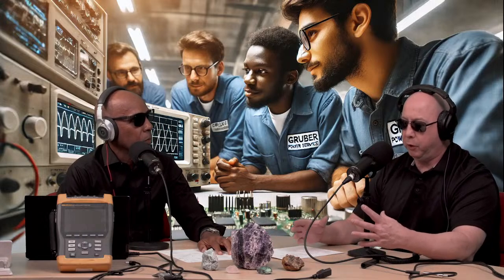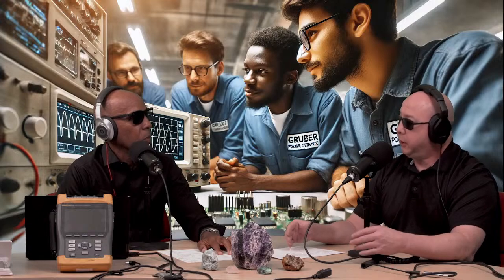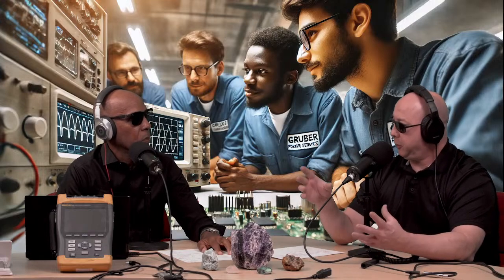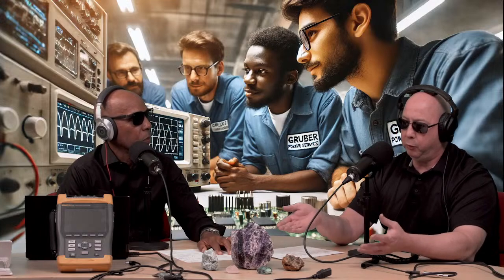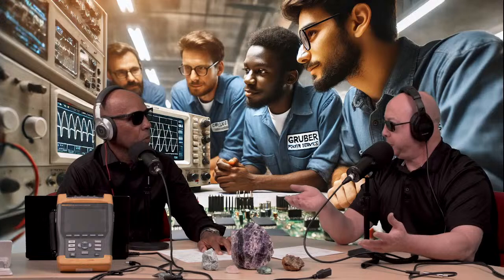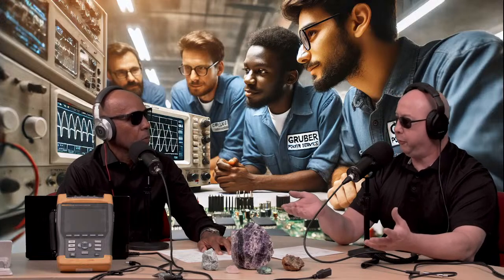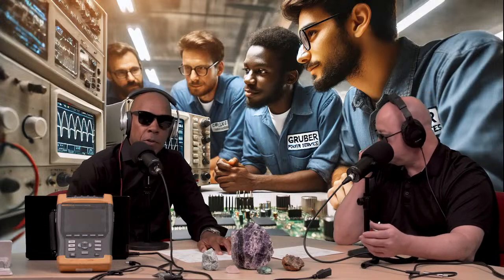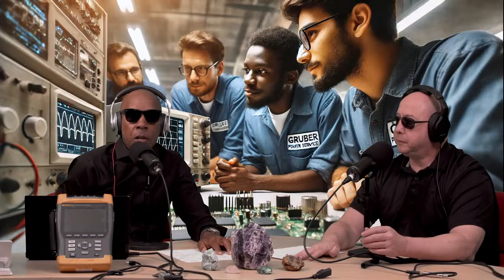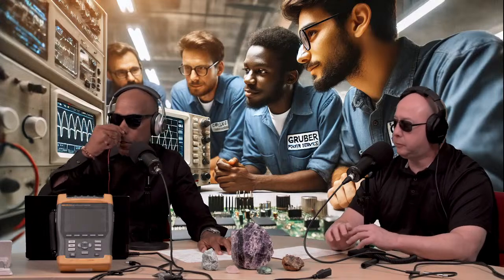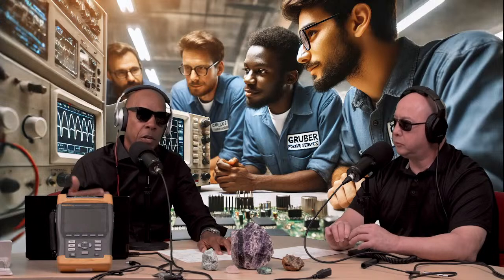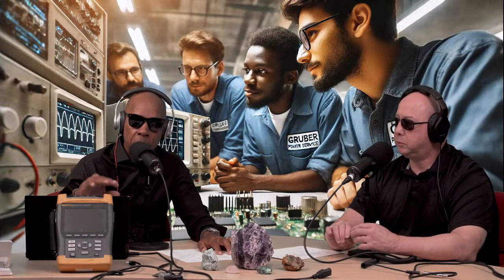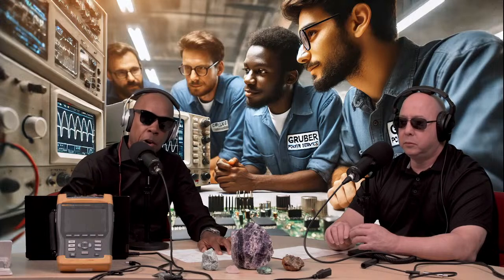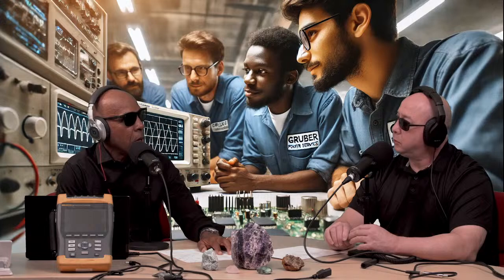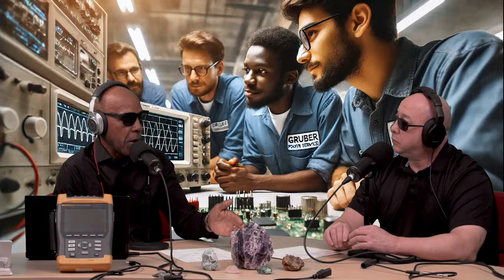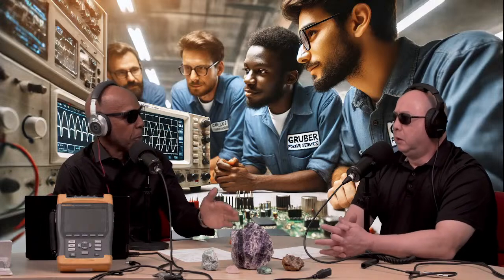We have a machine where we simulate equipment, so we'll hook up the output power to what we call a load bank. Then we'll turn that on and stress it, say 30, 40, or 50% load, and run that for 3 to 4 hours. That percentage refers to the capacity — 30% of the capacity, or the rated kVA of the unit. We're testing it at different levels and stresses to see if it will carry the load. So how long do you run the load test at 10%, 20%, 40%, or whatever the level is?